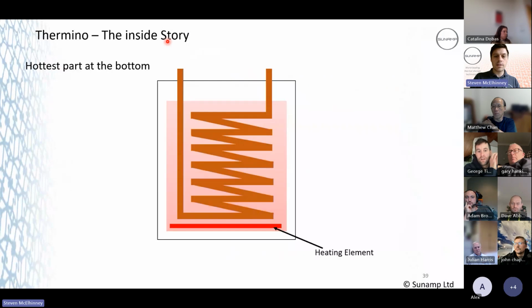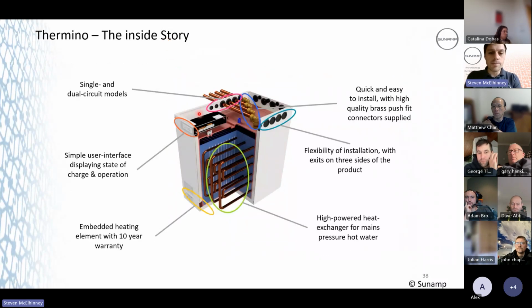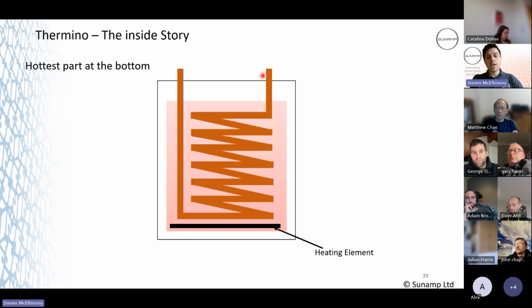Yeah, so let's go back to your cutaway. It's the whole capacity heat exchanger basically. If you think about the pipework, there's just an extra coil for that secondary heat exchanger running through the copper fins and stuff. So it's all part of the same heat exchanger block. That's what you mean, George, the same path, as it were. Both heat exchangers are kind of matched. So if you're plumbing into A and B, you're discharging from top to bottom. So basically, if your A and B is coming in here, that's essentially what you're getting top to bottom, if you're cutting it and releasing out that way.